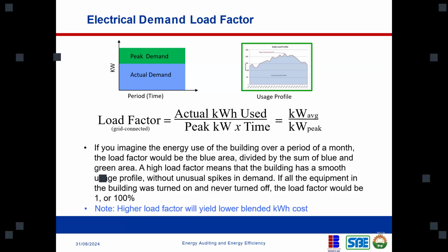The point I'm making is that in some places you may be faced with the challenge of calculating demand charges, demand consumption, or demand capacities of a facility. This is important: if you're sizing a generator, you need to pay attention to the demand of the facility.